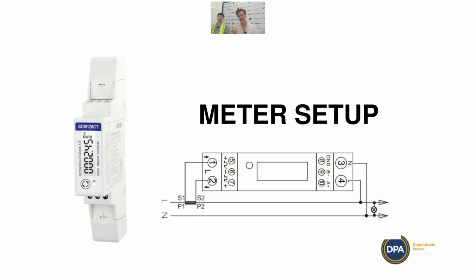You need to put a fuse on the active. People sometimes use these little inline ones from Jaycar. You might want to put some heat shrink around it to make sure it's rated to 240, or you could just use a circuit breaker if you have enough poles. Don't wire the active and neutral into the bottom instead of the top, because that will blow it up, which is what I did in the workshop the other day.